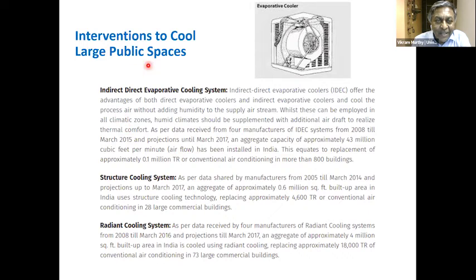We can use many other interventions. I've taken this from the India Cooling Action Plan released by the Ministry of Environment - you must all read it. One way is indirect-direct evaporative cooling: you first dry the air without exposing it to moisture, then cool it, and you can get very low temperatures, lower than the wet bulb. That's a beautiful thing - naturally cooling, in a place like Pune you can get 21 degrees centigrade leaving air, whereas the wet bulb might be higher, 23 or 24.